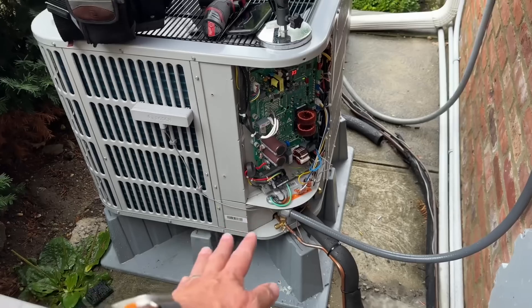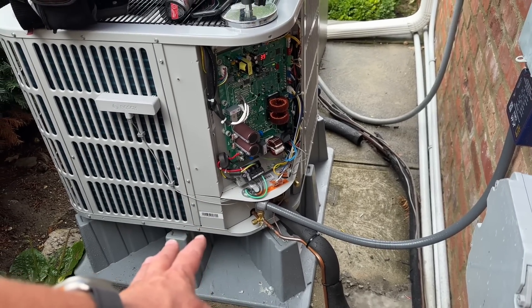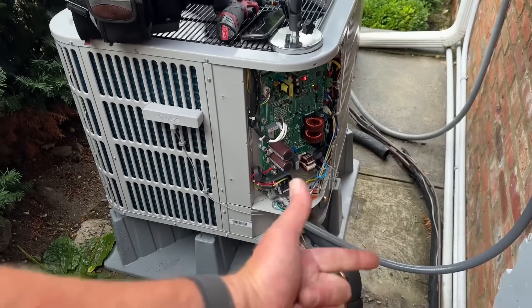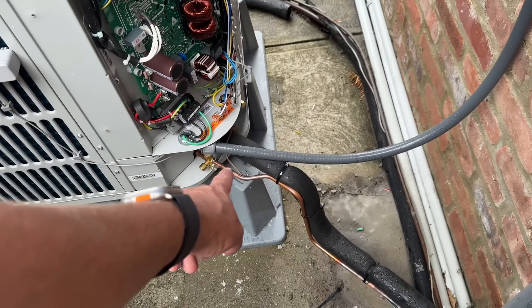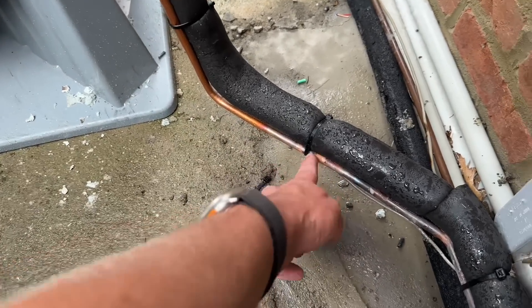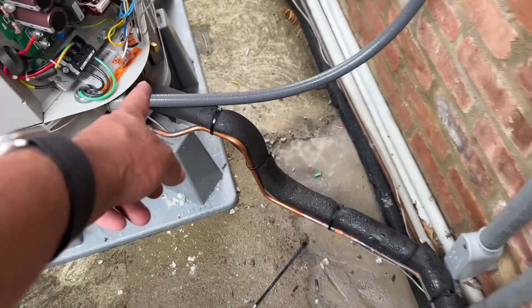We have our heat pump condenser on a Diversitech high-rise pad — this is made for heat pumps, designed to save time, save money, and really makes it look like a nice, sweet job. We took our three-eighths liquid line, put some nice bends on there, we brazed — there's our one joint right there, not a coupling but we swedged that — and we have our three-quarter as well. Looks really, really nice.